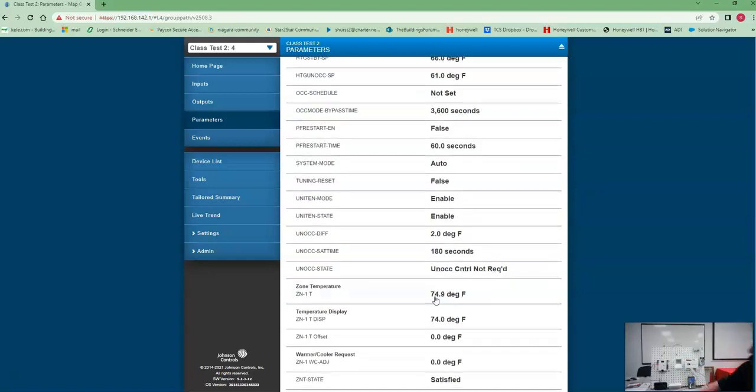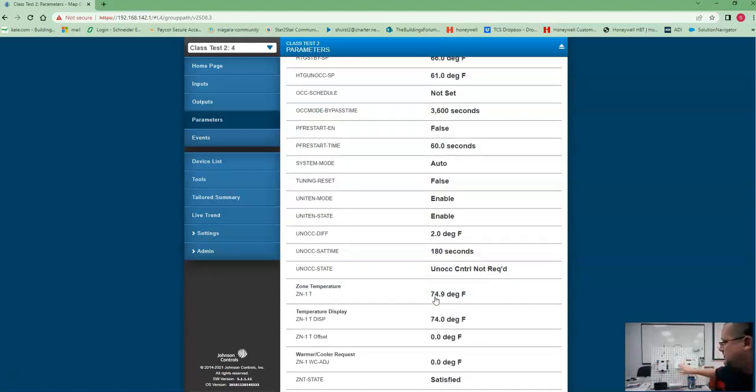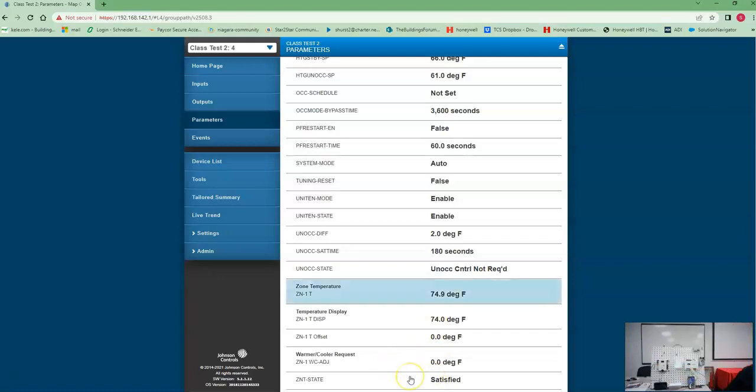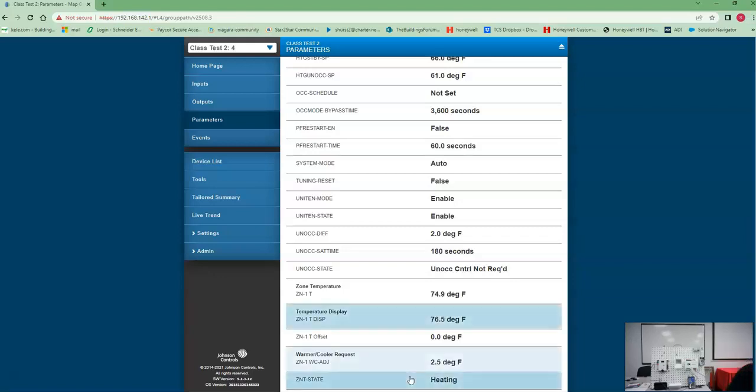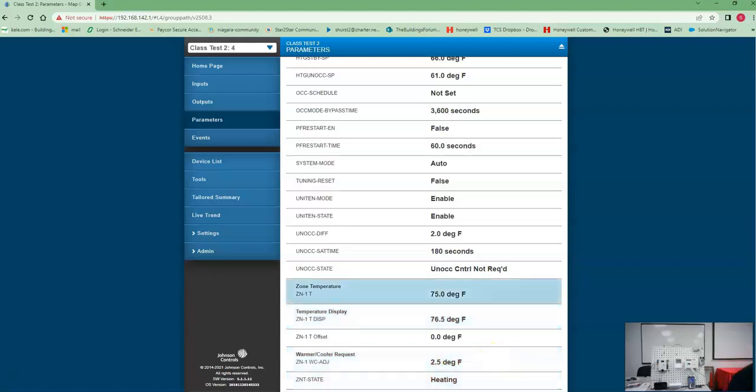And we got warm/cool adjust. So we programmed this one to be warm/cool adjust. So there's 2.5 up. We look down here at warm/cool adjust, we should see this climb to 2.5. Let's give it a second to see if it comes through. Obviously there's a little bit of time delay in between the communication. There it is, 2.5, changed over to heating mode. So you're seeing live values in this controller.